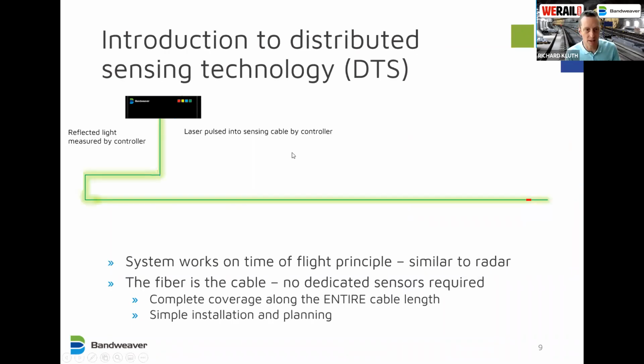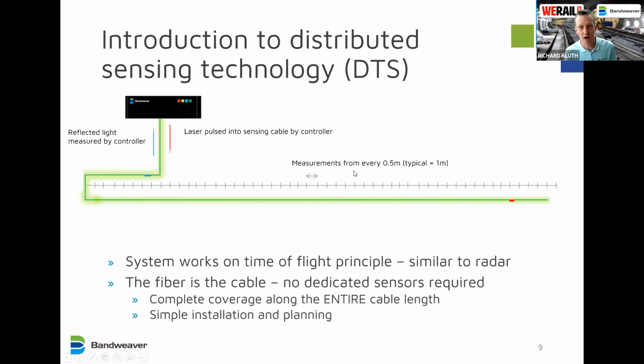So if we look at the typical setup, stripped down to its basics, you have the linear heat detection controller here, the box, and a cable that plugs into the box. The system sends a light pulse into the fibre. The laser pulse interacts with the fibre, and some light is reflected back to the controller. The time it takes for the reflected light to return gives the precise location, which is a very similar principle to radar. And by analysing the power and frequency of the reflected pulse, the controller is able to determine the precise temperature information at all points along the fibre. Depending on the sampling range and frequency of the system, how it's set up, you can get measurements from every half metre to a metre. Typically 1 metre is the standard.